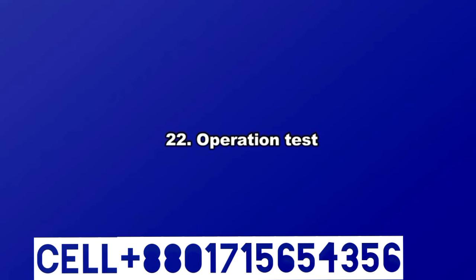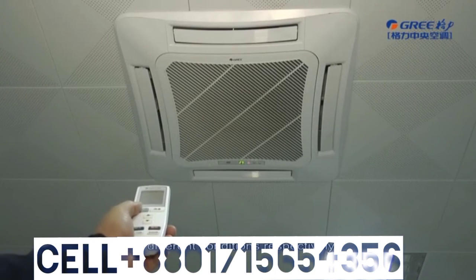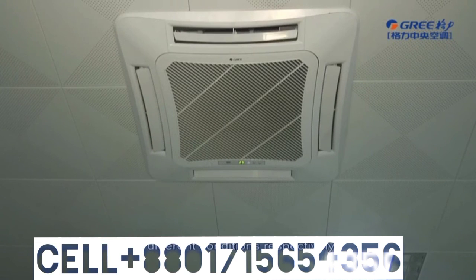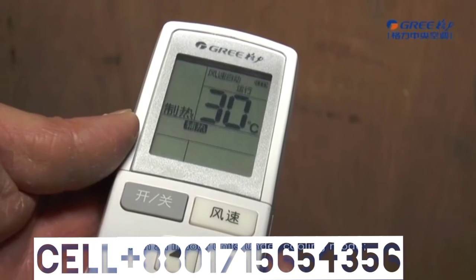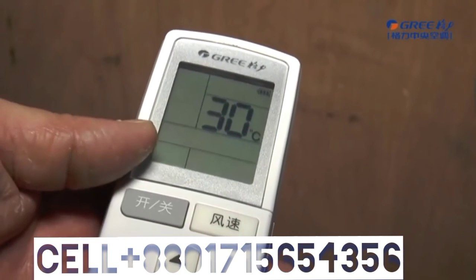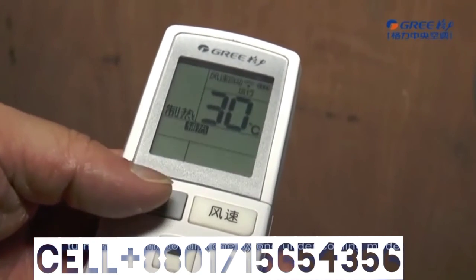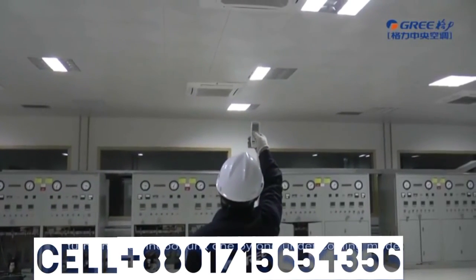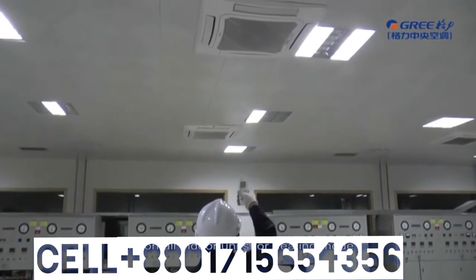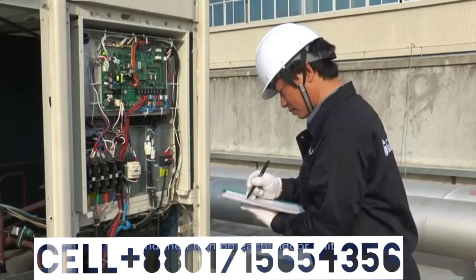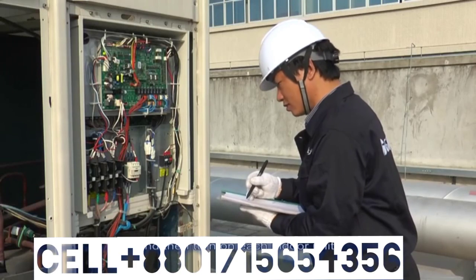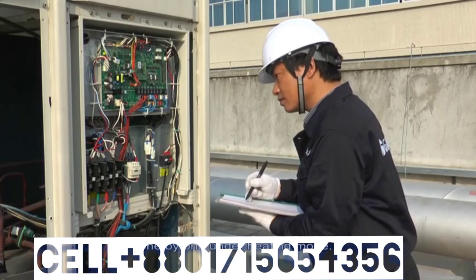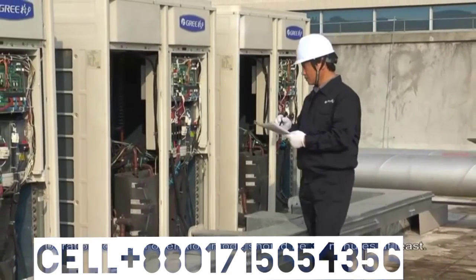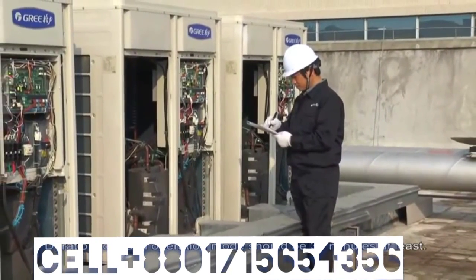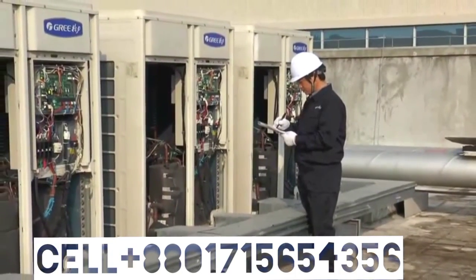22. Operation test. Start the units for debugging in different conditions respectively. Turn on all indoor units under cooling mode. Turn on each indoor unit one by one under cooling mode. Turn on all indoor units for heating mode, and then turn on each indoor unit one by one under heating mode. Duration for each operation mode should be 30 minutes at least.